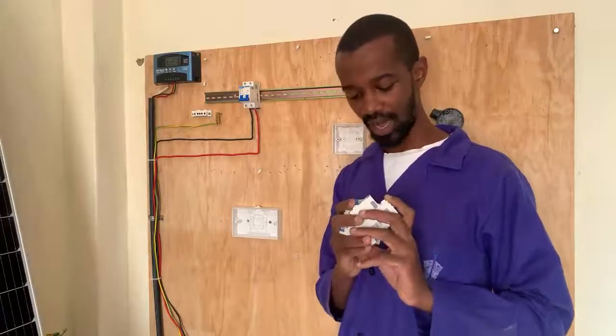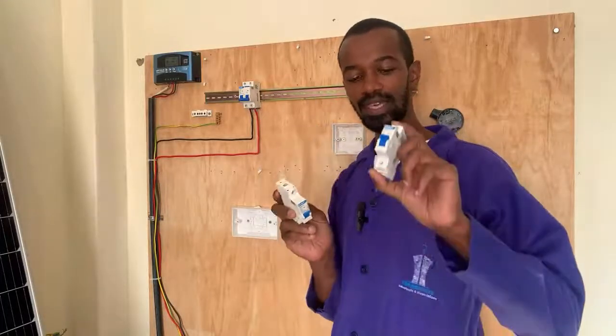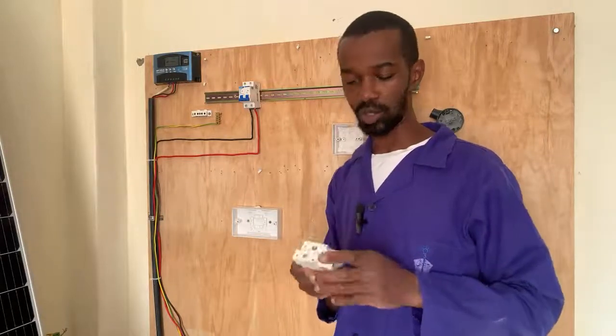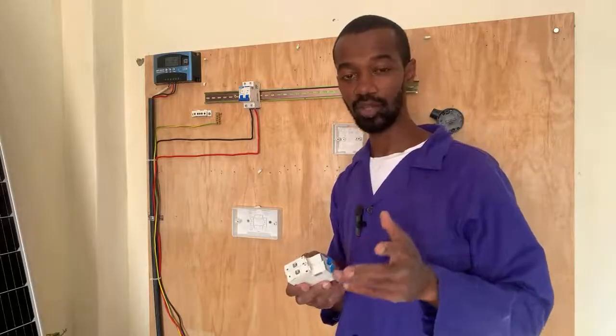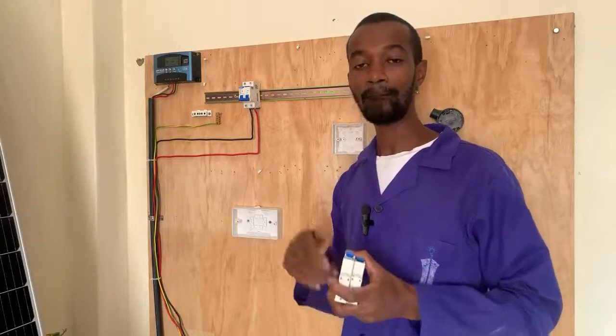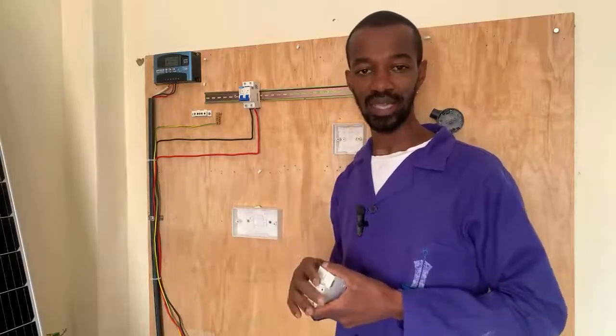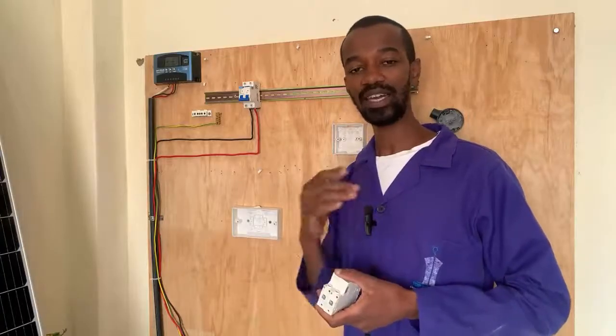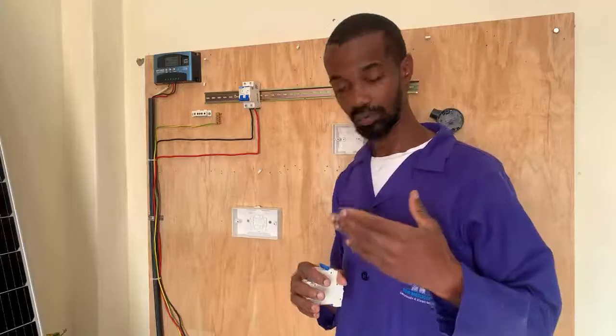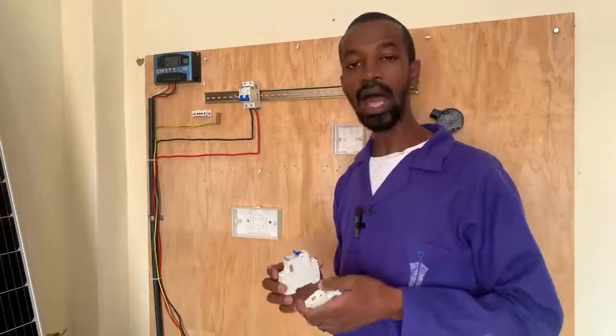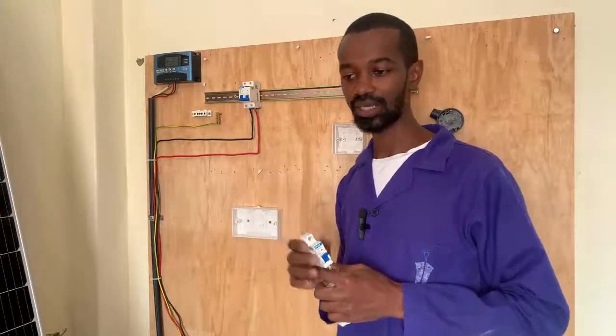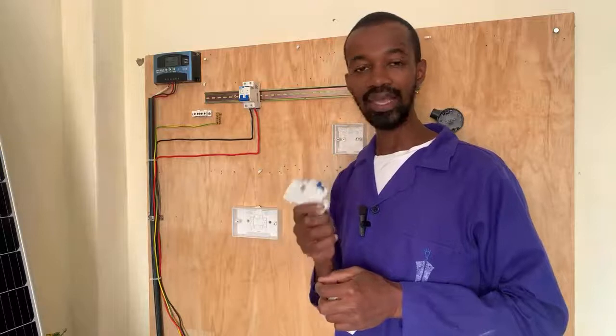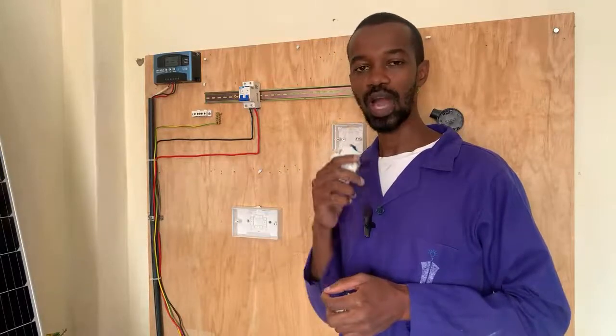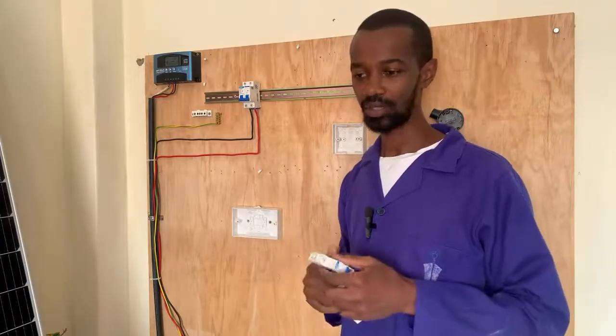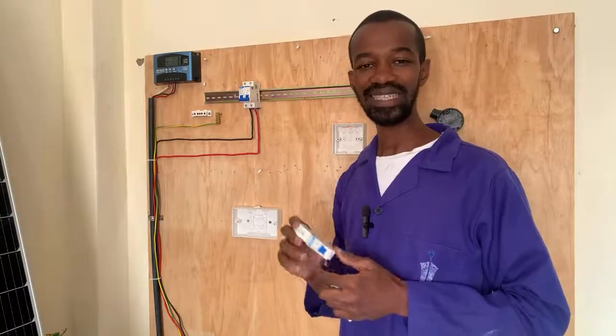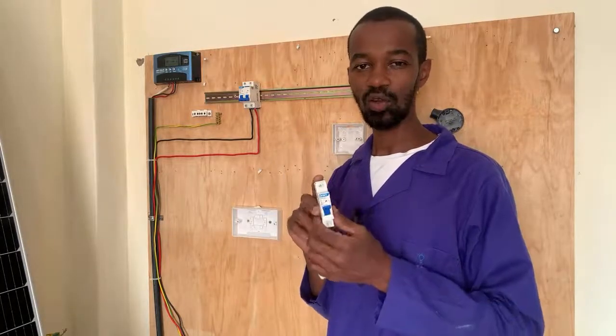So I'll have a 20 ampere MCB and a 6 ampere MCB for my lighting. You can have something lower than that if connecting fewer points, but if connecting multiple points, say a ring circuit for the socket, which we'll cover, you can have something bigger than 20 for the sockets. If you have a lot of lighting points connected to that circuit, you'll require an MCB bigger than 6. We also have a 10, and a 16. So depending on the number of lighting points, that dictates the ampere or size of the MCB.